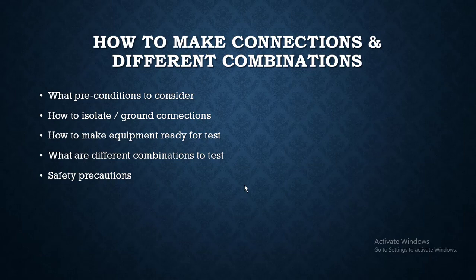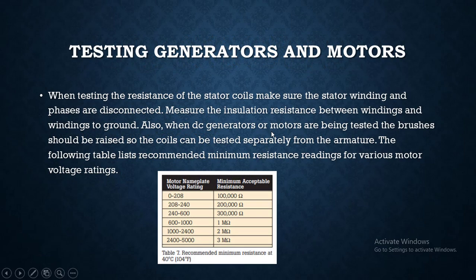When testing generators and motors, make sure the stator winding and phases are disconnected. Measure the insulation resistance between winding and winding to ground. When DC generators or motors are being tested, the brushes should be raised so the coils can be tested separately from the armature.